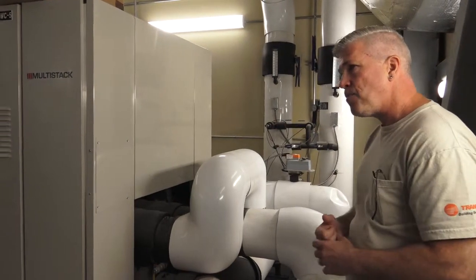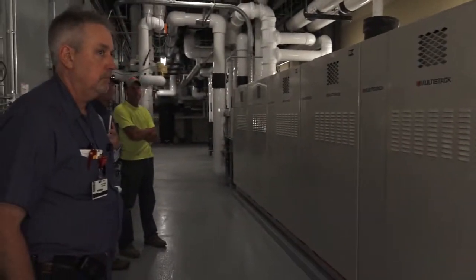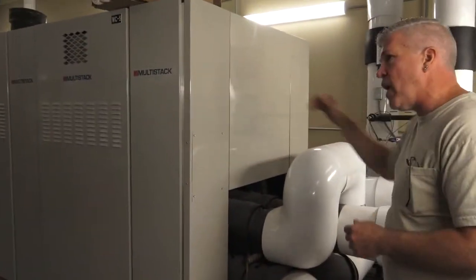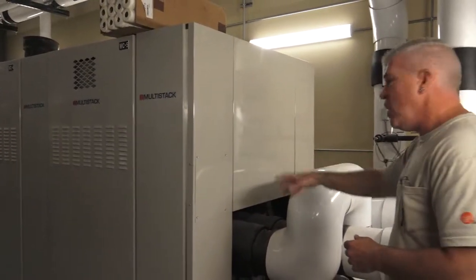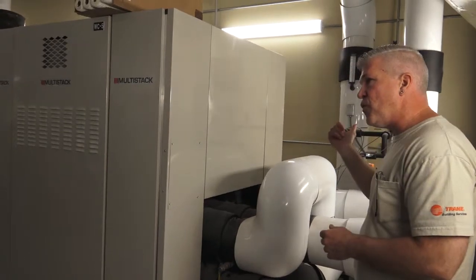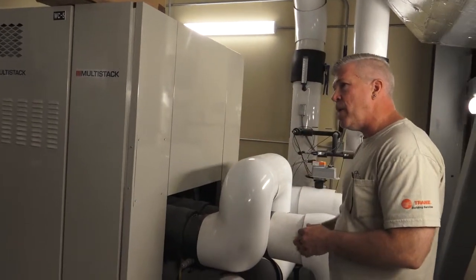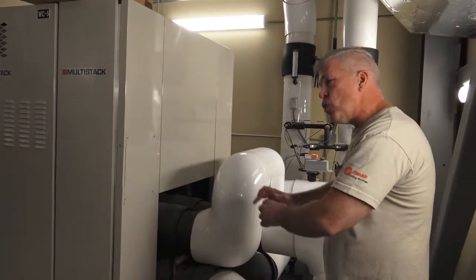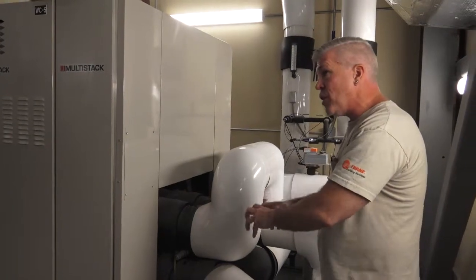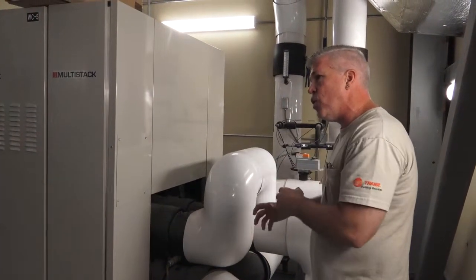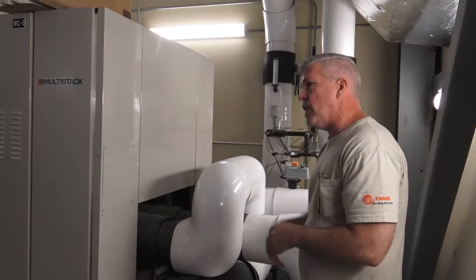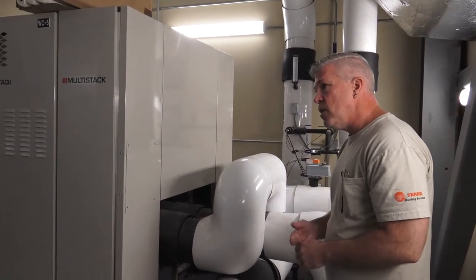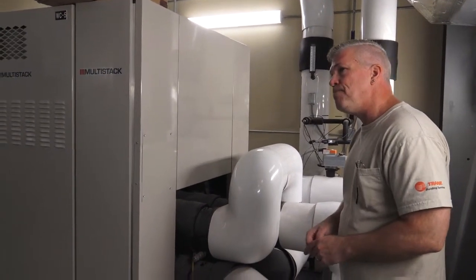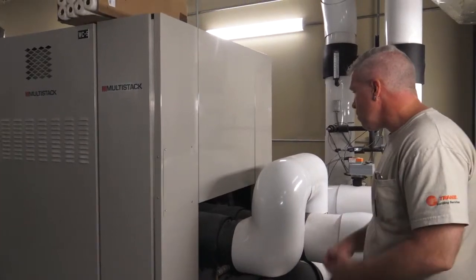So you're fed from both sides—the chilled water side and the hot water side run at the same time, and the third pipe goes out to the geofield. The mixing valves determine where it dumps hot water, chilled water, or both at the same time, whatever it needs to maintain the supply temperatures. It's pretty cool—you guys have them all over the place.